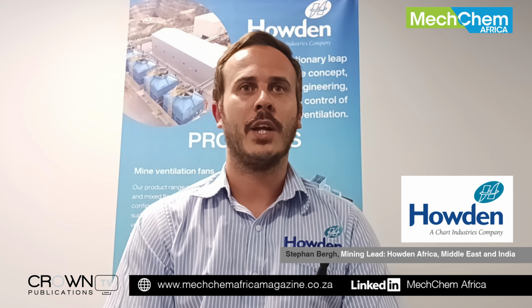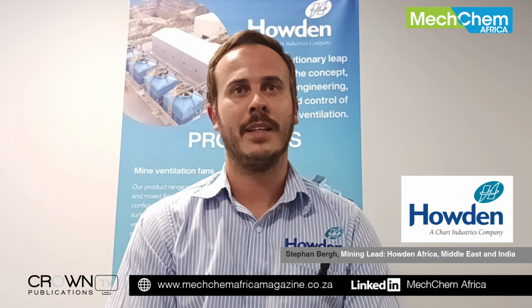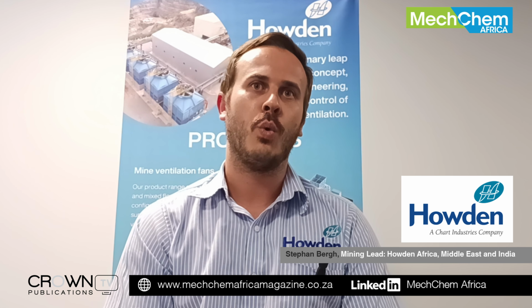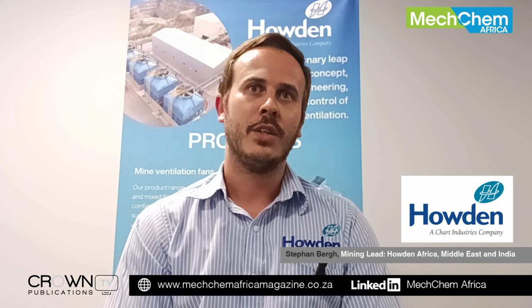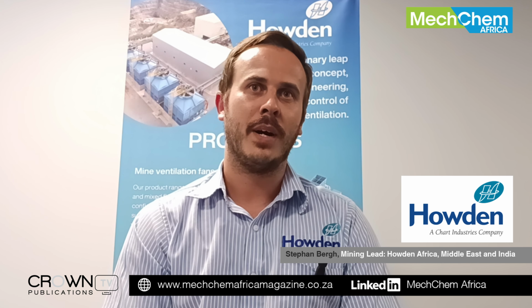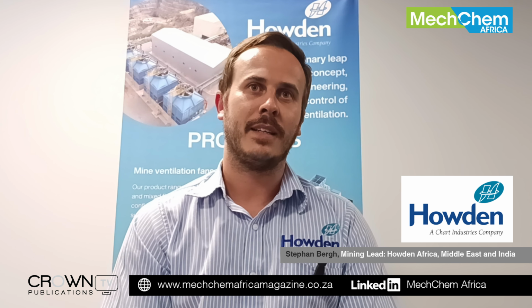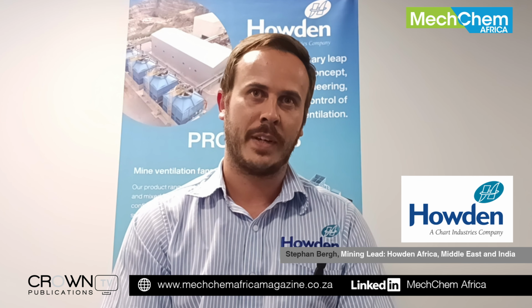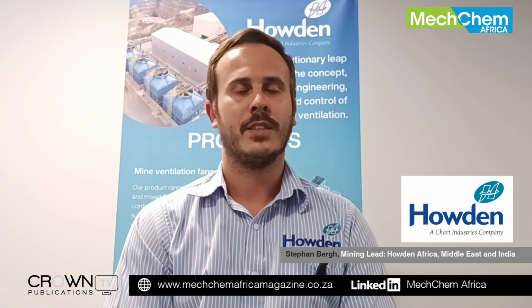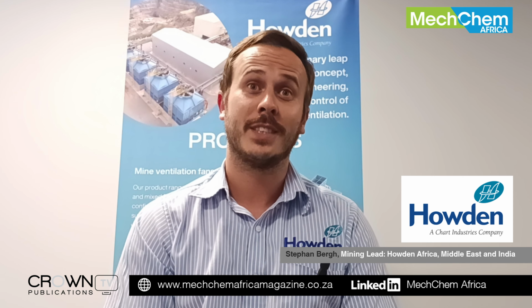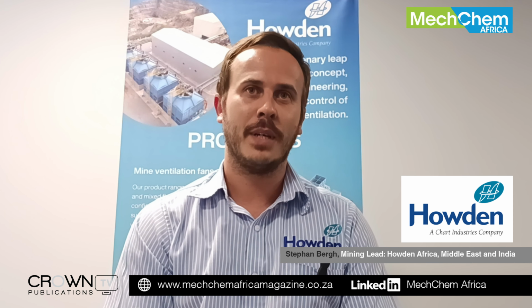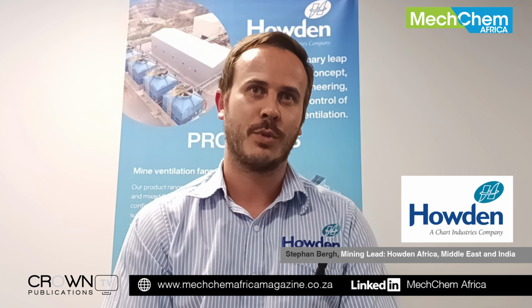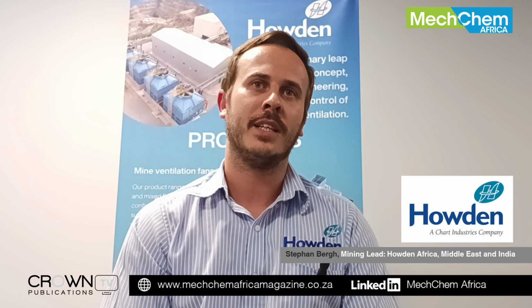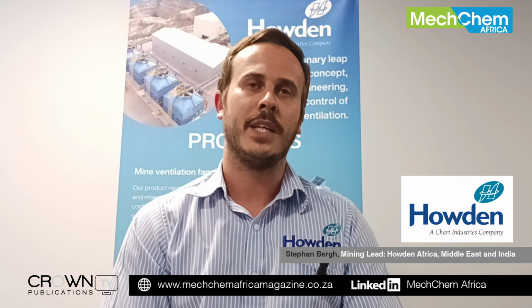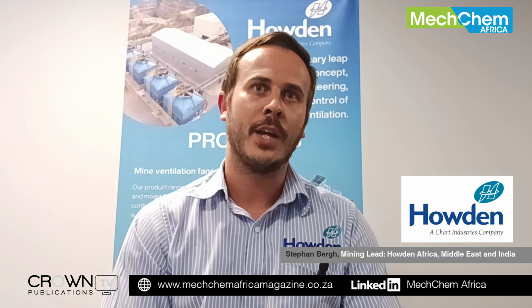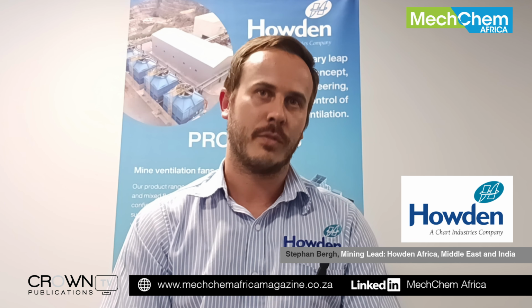An optimized ventilation solution will identify periods in a day where there's reduced activity or where conditions allow the system to be modulated to optimize airflow at certain levels based on either levels of activity or conditions underground. So I think the term ventilation on demand, which is something that you hear quite a bit these days, is a misnomer. In our case, in Ventsim CONTROL, ventilation on demand is a level of control within the software, but there's a lot that can be done to optimize a ventilation solution before getting to that level of control.